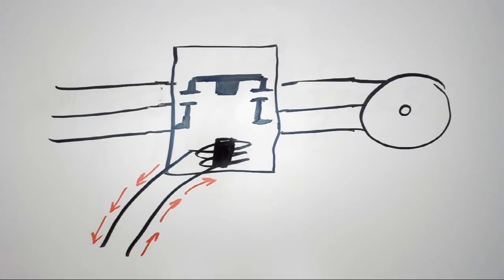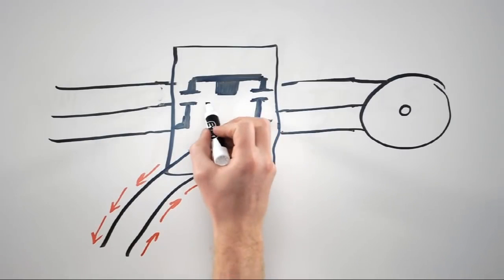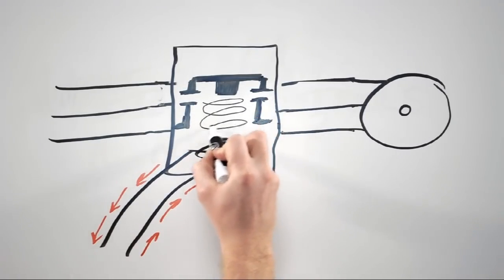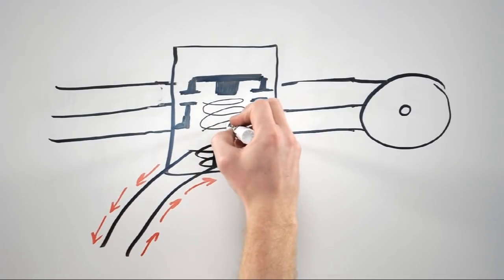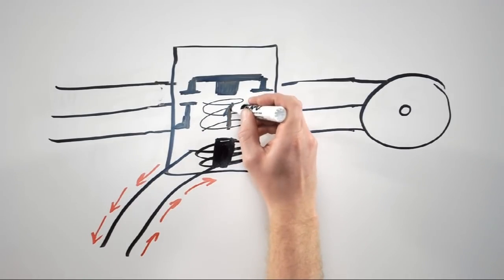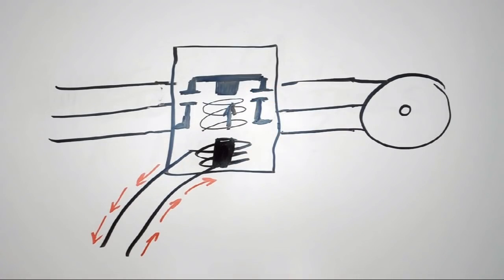But that's not enough to separate the electrical contacts. There is a spring inside the contactor. When the electromagnet is turned on, the top piece of metal overpowers and compresses the spring. But when the electromagnet is turned off, the spring is able to push apart the electrical contacts.